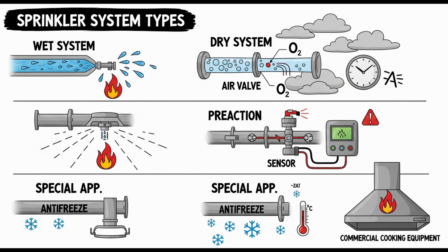Redundancy and fail safety seem paramount. The system must be designed so that a failure in the dry pipe sprinkler portion, like a broken pipe out on the pier exposed to cold, does not prevent the detection system from still functioning as an automatic fire alarm. Okay, so even if the pipe breaks, you still get an alarm signal from the detectors. Right. And conversely, a failure in the detection system does not prevent the system from operating as a conventional automatic dry pipe system, triggered solely by a sprinkler head activating due to heat. So if the pipes break, you still get an alarm. If the detection fails, the sprinklers still work like a standard dry pipe system when they get hot enough. It's layered protection, belt and suspenders. Exactly. Really robust design philosophy for these critical infrastructure locations. A manual means to operate the detection system is also required at accessible locations, generally within 200 feet of travel distance. Manual trigger capability. Yes.